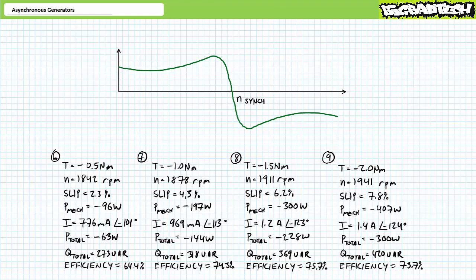This exercise also served to demonstrate how supremely easy it is to make an asynchronous generator. All I needed was an existing three-phase AC connection and a prime mover with sufficient strength to turn the rotor of an off-the-shelf squirrel cage induction motor faster than the synchronous speed. At no point did I have to synchronize voltage magnitude, frequency, and phase shift with the grid, or make any perfectly timed connections. The squirrel cage induction machine is entirely capable of seamlessly switching from one mode to the other — motor or generator. Asynchronous generators are an extremely inexpensive means of converting the mechanical power of moving wind, falling water, or expanding steam into electrical power for industrial or commercial use.